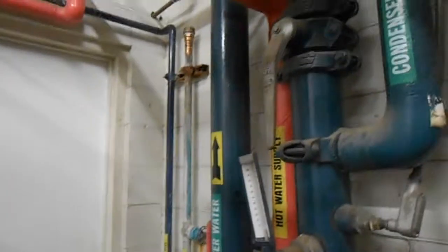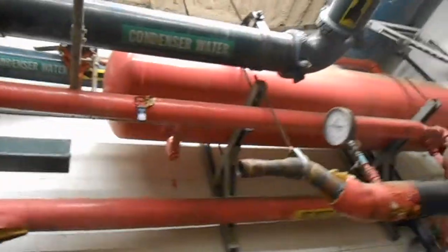So we're going to pump hot water directly into the VAV loop at about 140°F. And then we're going to pump it into an exchanger until the condenser loop reaches about 60-65°F. It doesn't have to be that hot for the heat pumps to work in the winter. It's going to be looking at one of these two thermostats here. There's going to have to be a solenoid valve or something — it'll close off the water source heat pump loop because it will get warm fairly quickly. The VAV loop will need pretty much constant hot water, so the recirc pump is going to go right back in here. It'll be all cleaned up — ninety degree angles and stuff. And the next project in here, this panel is going to go away and all of this we're going to put in a new control panel that's going to do everything — it'll have all the small contacts with everything.